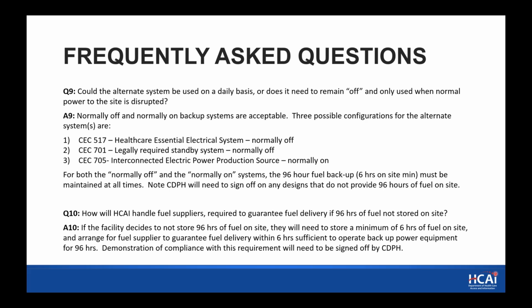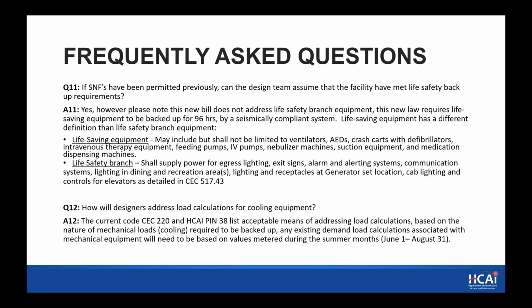Next slide. Question 11. If SNFs have been permitted previously, can the design team assume that the facility has met life safety backup requirements? Yes. However, please note, this new bill does not address life safety branch equipment. This new bill requires life-saving equipment to be backed up for 96 hours by a seismic compliance system. Life-saving equipment has a different definition than life safety equipment.